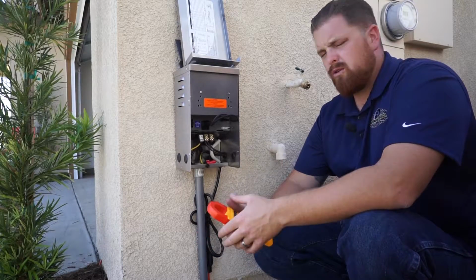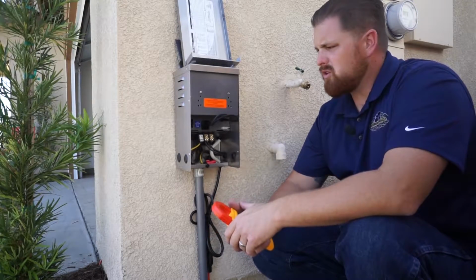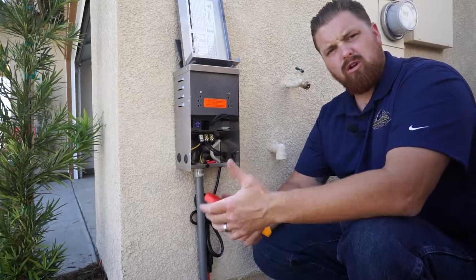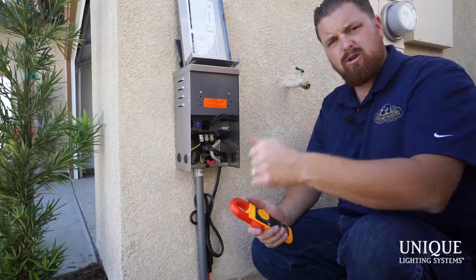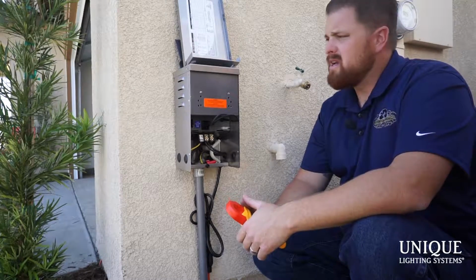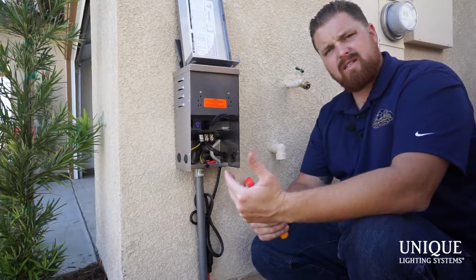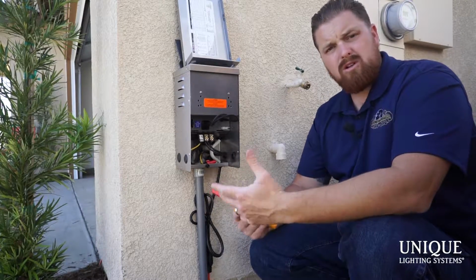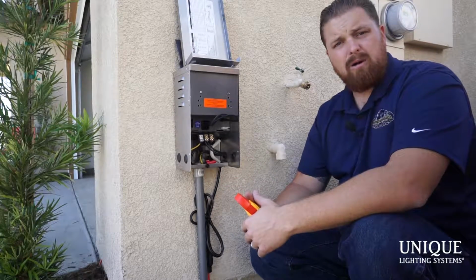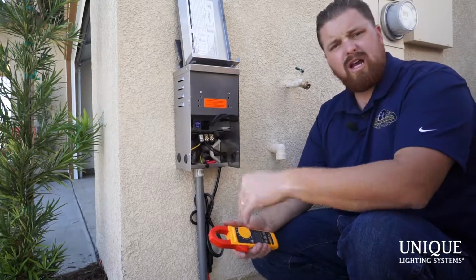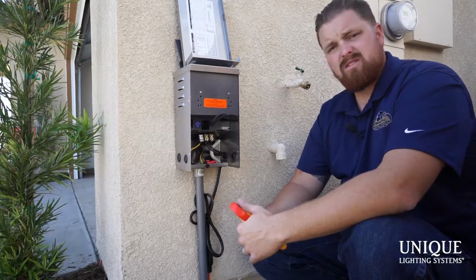Okay, so we're back. After we've hooked everything up, we've walked around, we've made sure that all the lights are on. Now we're going to do what's called the critical three. So the first of the critical three is checking your primary amperage. And again, when I say primary and secondary, the difference is primary is always going to be your 120 volt power, and your secondary is going to be your low voltage side, your 12 volt side, or in some cases even some 24 volt stuff.